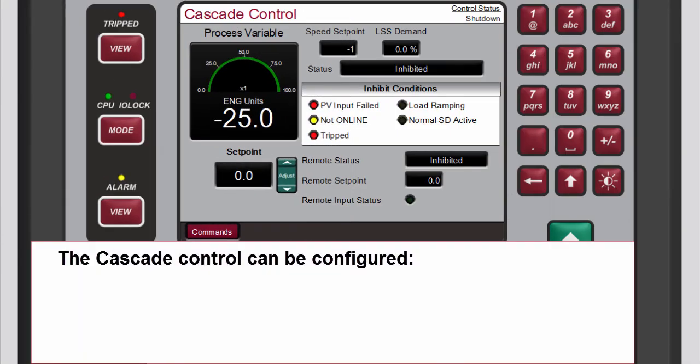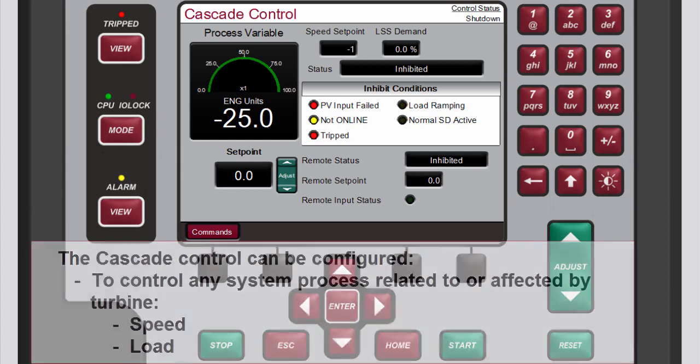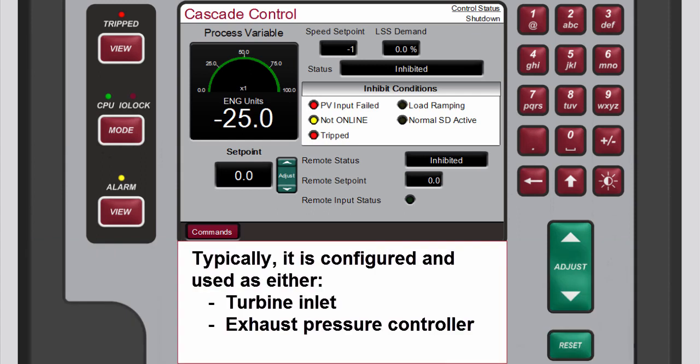The Cascade control can be configured to control any system process related to or affected by turbine speed or load. Typically this controller is configured and used as a turbine inlet or exhaust pressure controller.